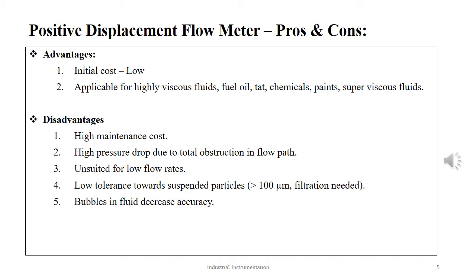However, the limitations of these flow meters are: high maintenance cost, high pressure drop due to total obstruction in flow path, unsuited for low flow rates, low tolerance towards suspended particles more than 100 micrometers, and bubbles in fluid decrease the accuracy.